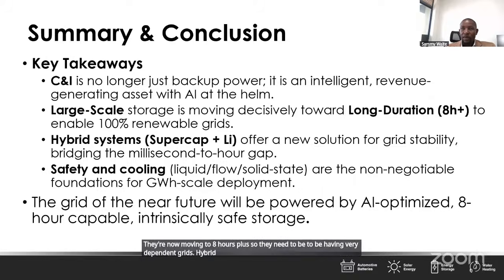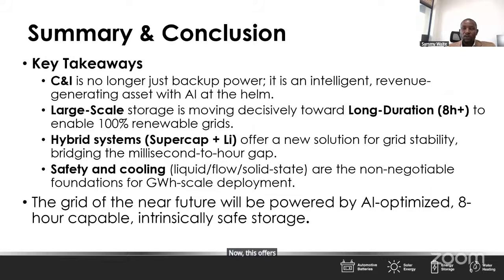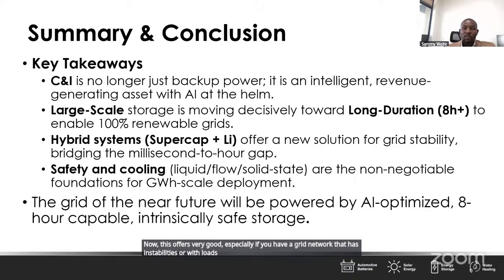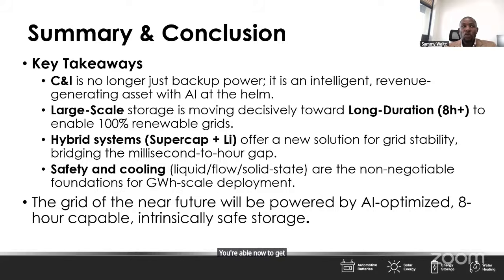Hybrid systems - we've talked about supercaps being integrated together with lithium ion. This offers very good performance, especially if you have a grid network with instabilities or loads that are not very stable with peak loads. If you have a hybrid system integrating lithium ion with supercapacitors, you're able to get a smooth grid with very stable voltages and frequency.